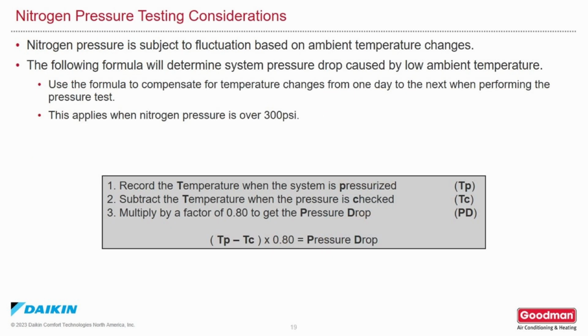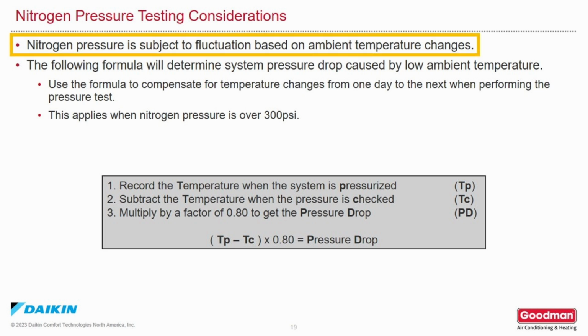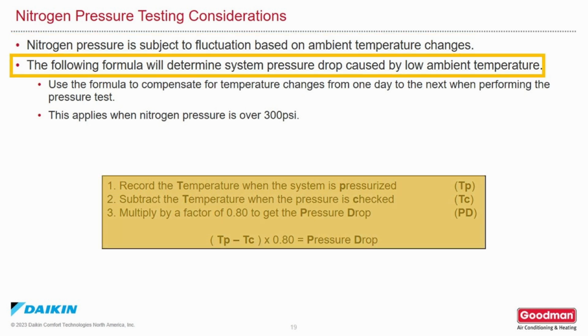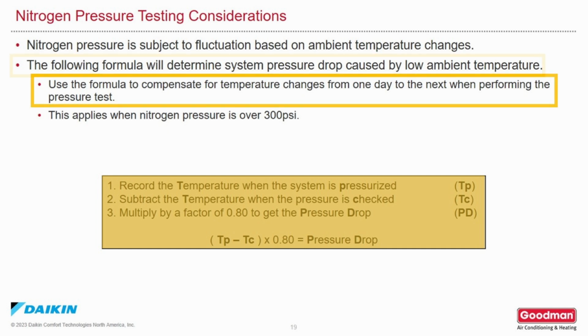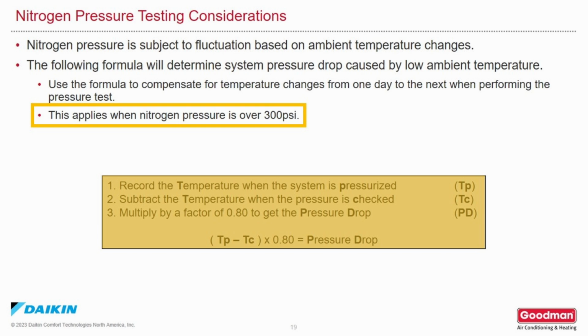Here are a few things to consider when doing a nitrogen pressure test. Nitrogen pressure is subject to fluctuation based on ambient temperatures, not as much as air, but still subject to fluctuation. The formula below will help determine system pressure drop caused by low ambient temperatures or a change in temperature. Use this formula to compensate for temperature changes from one day to the next when performing a pressure test. This applies when nitrogen pressure is over 300 psi.